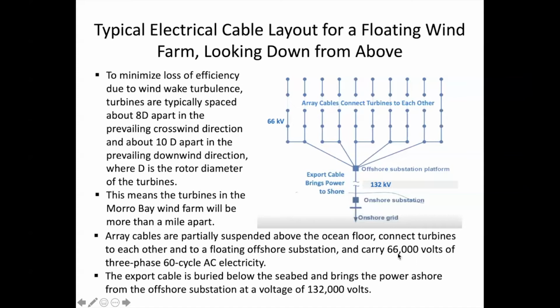The array cables will carry 66,000 volts of 3-phase 60-cycle AC electricity, all coming together at the offshore substation. From there it's sent ashore via an export cable buried under the seabed, bringing power ashore at Morro Bay from the offshore substation at 132,000 volts.